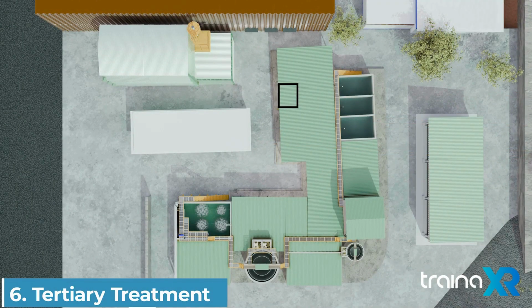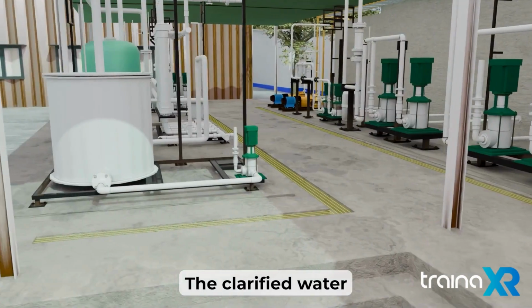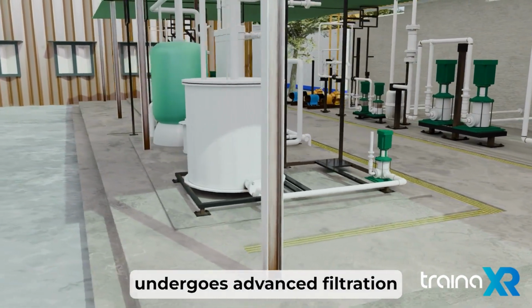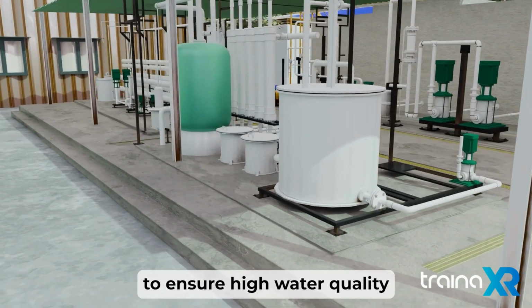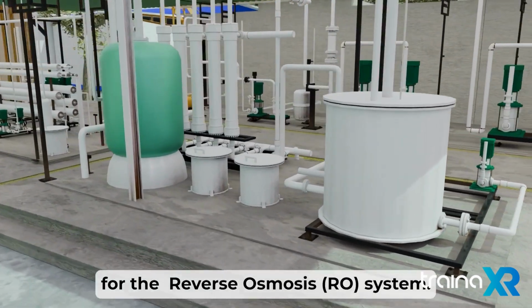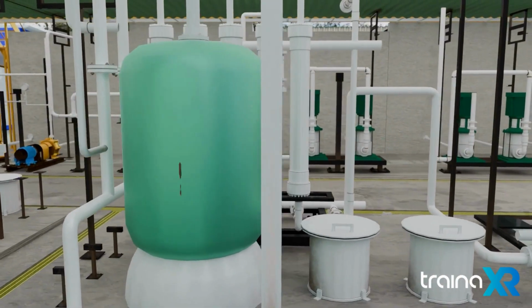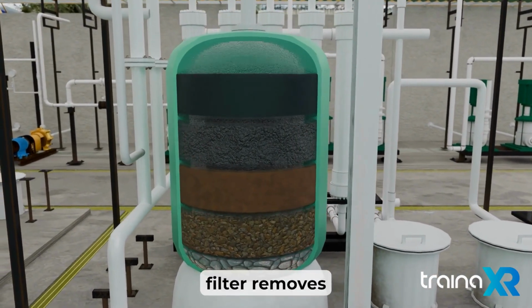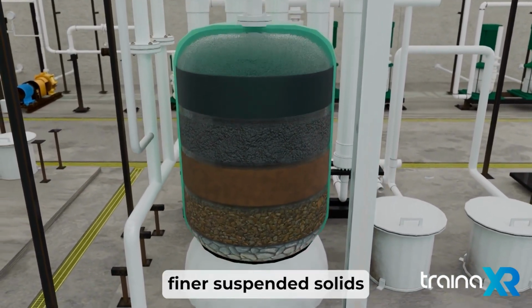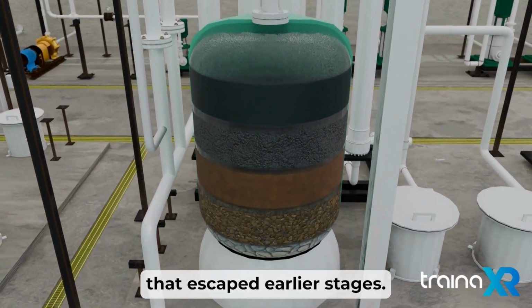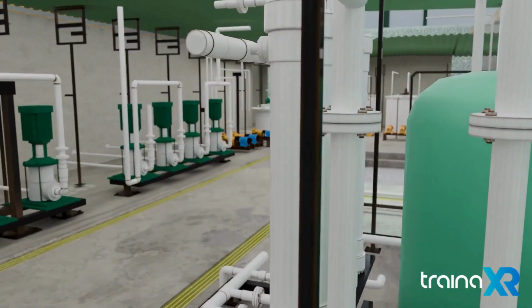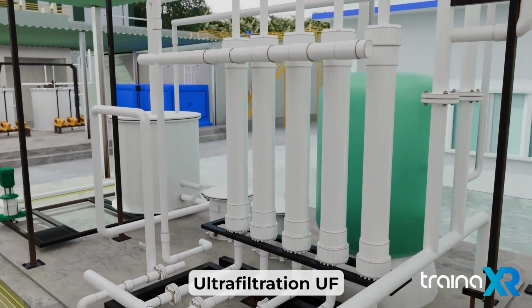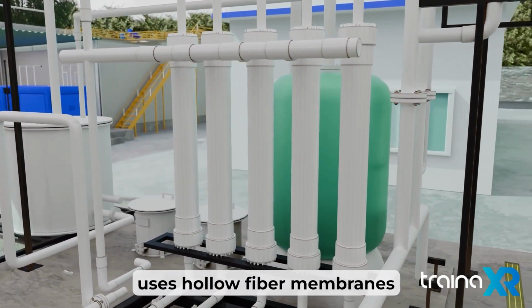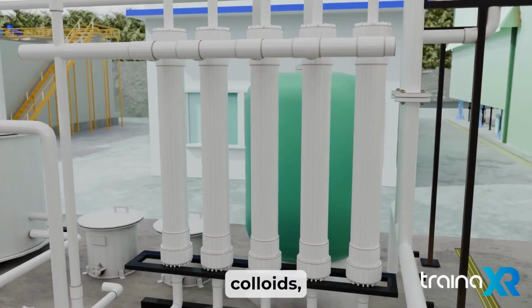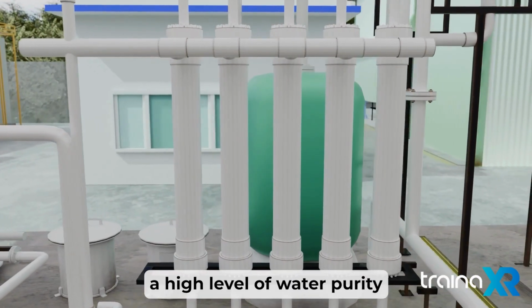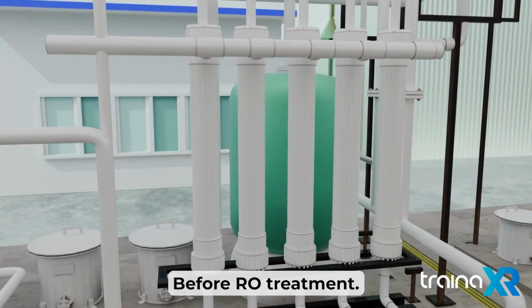Tertiary treatment. The clarified water from the primary treatment undergoes advanced filtration to ensure high water quality for the reverse osmosis (RO) system. Pressure sand filter removes finer suspended solids that escaped earlier stages. Ultrafiltration (UF) uses hollow fiber membranes to remove microscopic particles, colloids, and microorganisms, ensuring a high level of water purity before RO treatment.